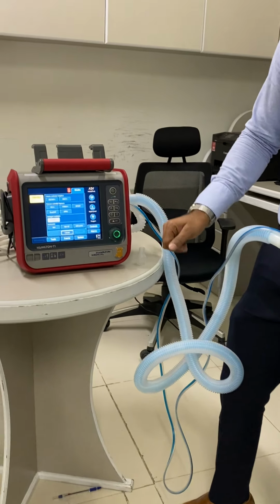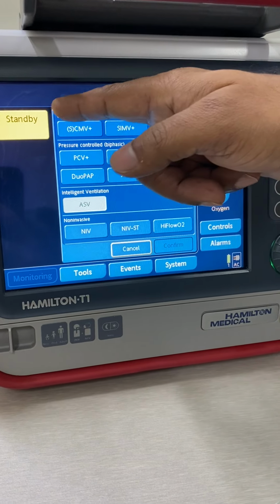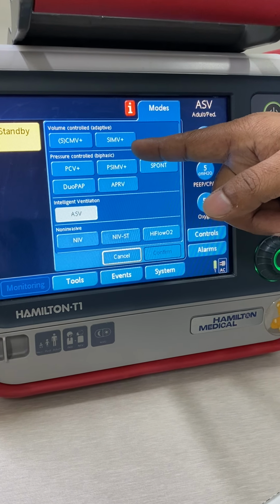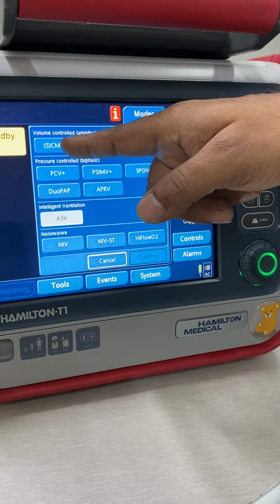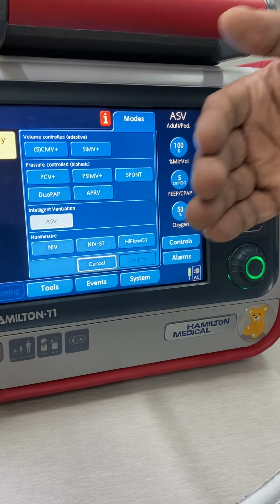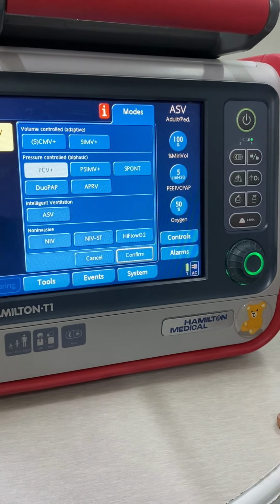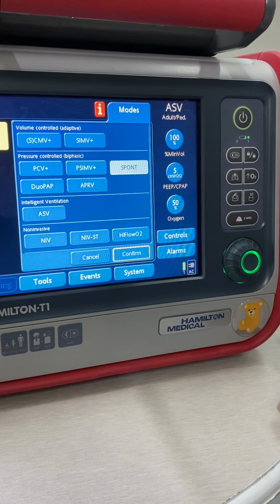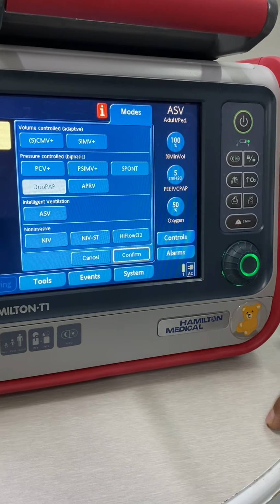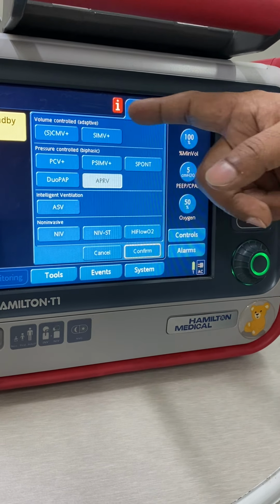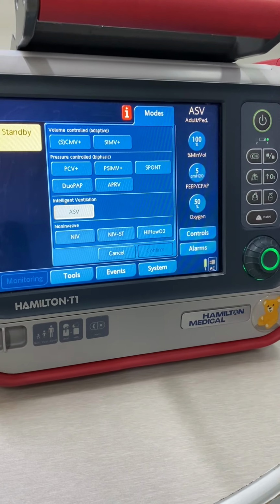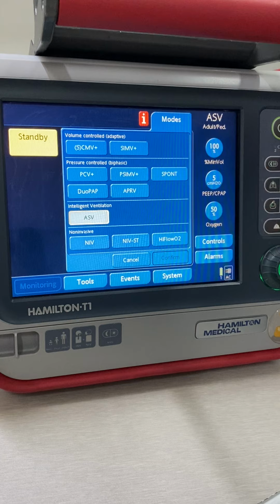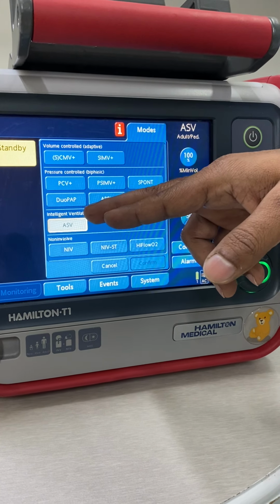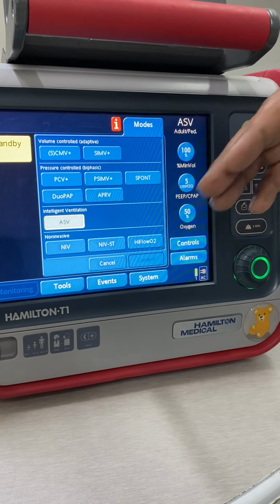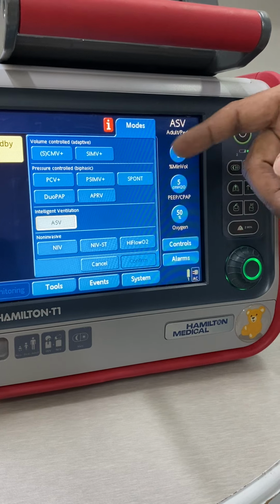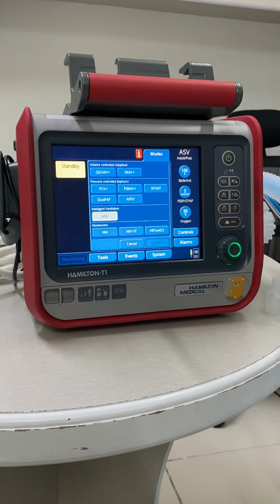If you want to choose a mode, go to the modes. We have all the available modes. We have the volume modes like CMV, controlled mandatory ventilation mode, and SIMV, synchronized intermittent mandatory ventilation mode. These both are volume modes, but there are also adaptive pressure modes, like the PRVC mode. We call it APV CMV and APV SIMV. We also have the pressure modes, pressure control ventilation mode and pressure SIMV. Spontaneous is CPAP with pressure support. DuoPAP is the BiPAP, and APRV is airway pressure release ventilation mode. These are all invasive ventilation modes. And we also have ASV, a unique feature from Hamilton, which is the automatic mode. You set up the minute volume percentage, PEEP, and FiO2, and the ventilator will go with the lung mechanism.